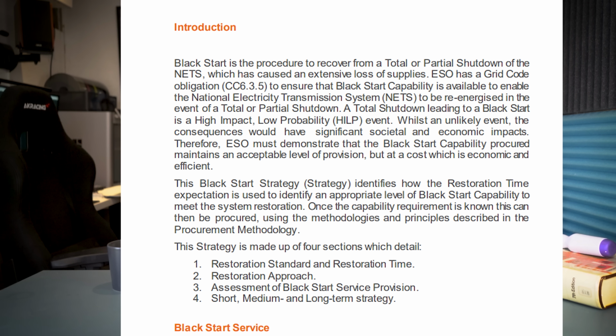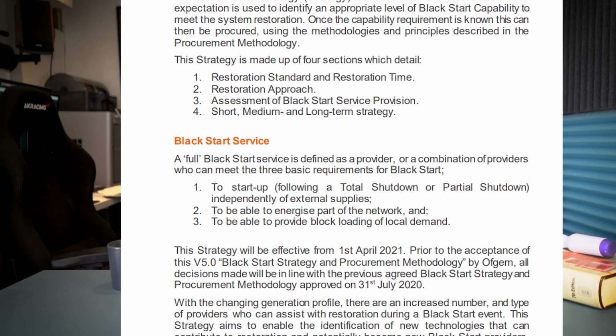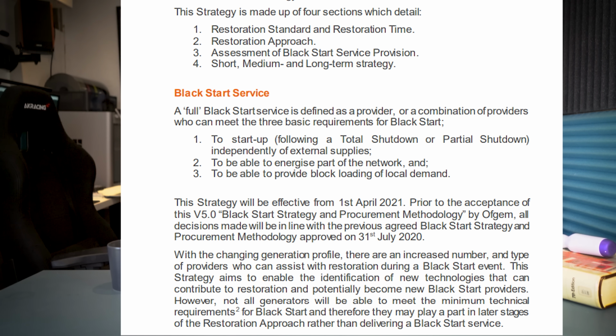In order to recover from a failure of the system, we need Black Start service providers, which are generators which meet a certain set of criteria to kickstart the grid. The Black Start service provider, or combination of providers, can start up following a total or partial shutdown, independent of external supplies. They need to be able to energise part of the network, and be able to provide block loading of local demand. So put simply, this means a generator must be able to start without needing power from the grid, and be able to meet the demand of its local area when connected to the grid.